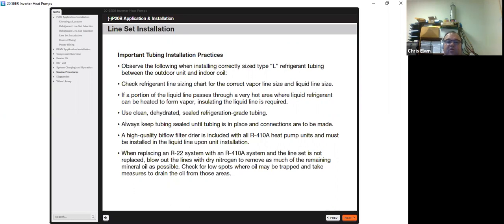When replacing an R22 system with a 410A system and the line set is not replaced, be sure to blow out the lines with dry nitrogen to remove as much of the remaining mineral oil as possible. Check for low spots where oil may be trapped and take measures to drain the oil from those areas. That is important. We did one several years ago, and the line set, it was hidden, but there was a huge trap in there, so the oil that we had come out of there was white.